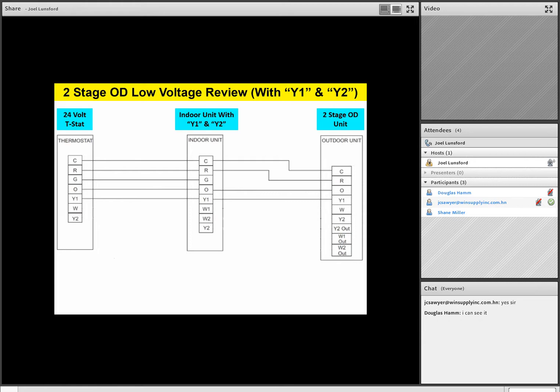Okay. Well, as you take a look at this little block diagram, let's go ahead and just start out with the fact that from the thermostat to the indoor unit, the indoor unit does have a Y1 and Y2 terminal. This could be a variable speed air handler. It could be a variable speed furnace. It could be a TM9Y. It could be a TM9E furnace. As long as they've got a Y1 and Y2 terminal, this wiring scheme would work.